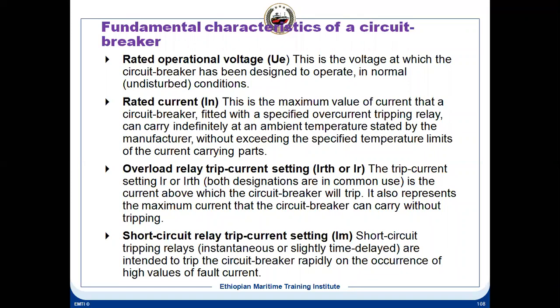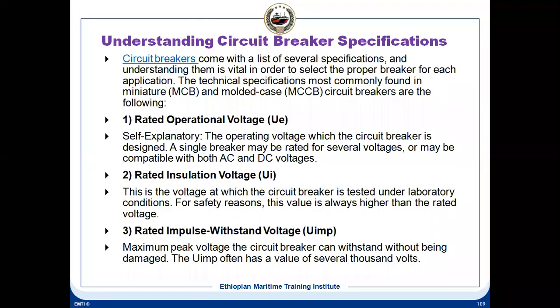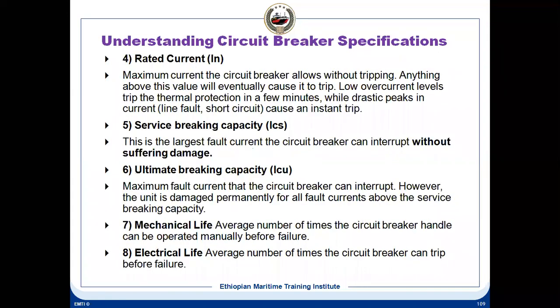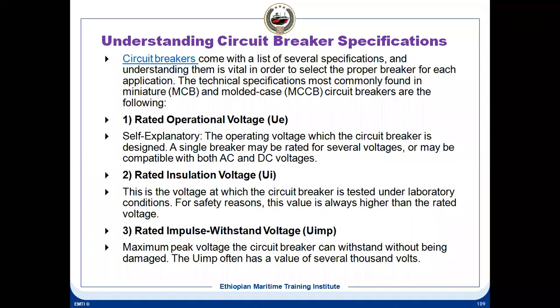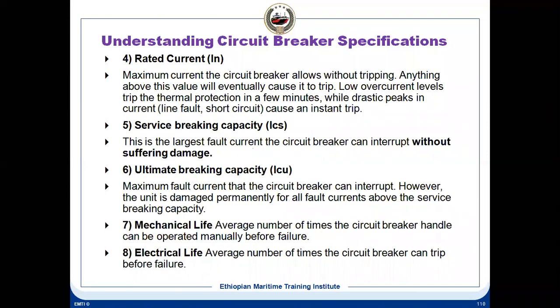Then the short circuit relay. The short circuit relay trip current is known as Im. Short circuit tripping relays are intended to trip a circuit breaker rapidly on the occurrence of a high value of fault current. So, understanding the circuit breaker specifications, as I told you: rated operating voltage, rated insulation voltage, rated impulse withstand voltage, rated current, service breaking capacity, ultimate breaking capacity, mechanical life, electrical life. These are the basic specifications you'll find. If a question is asked about what specifications you'll find on a circuit breaker, you can write all these points.